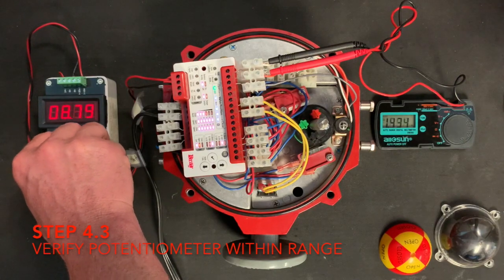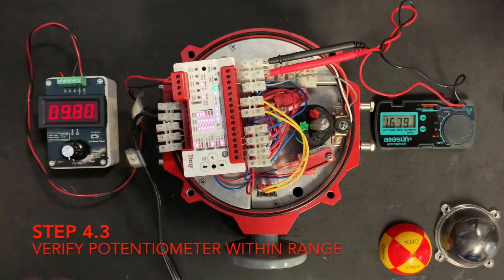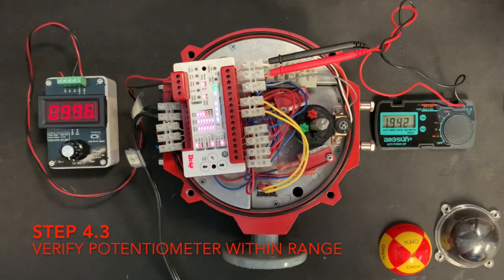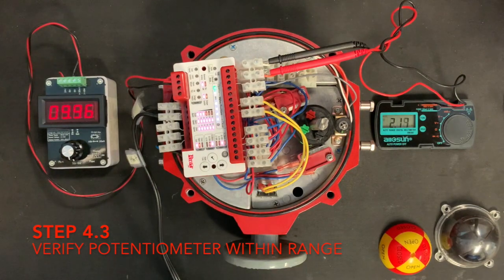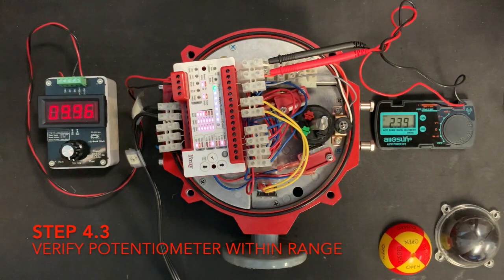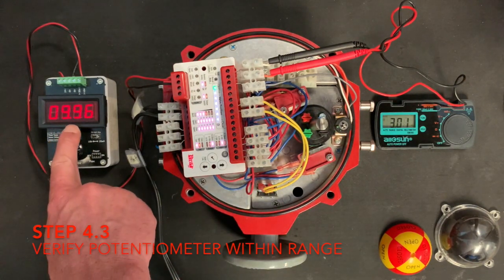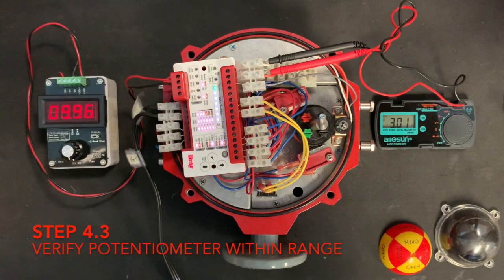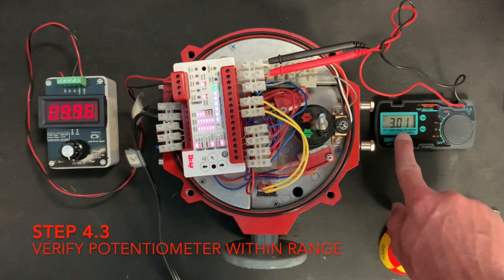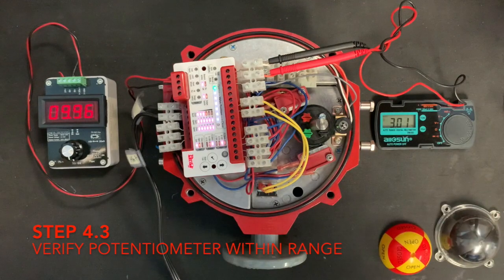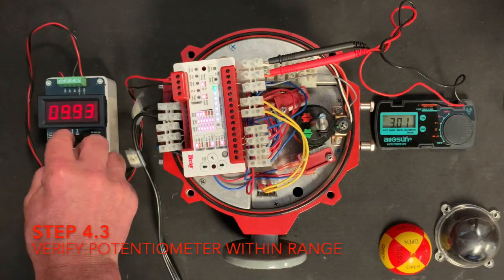For the closed position, the potentiometer voltage should be within 0.10 to 0.26 VDC. For the open position, the voltage on the potentiometer should be between 2.94 to 3.10 VDC.